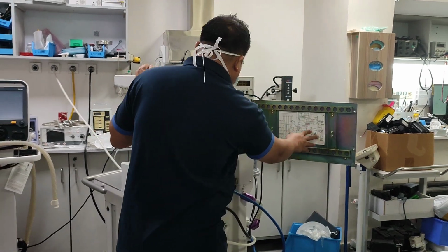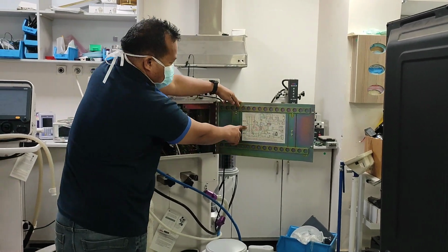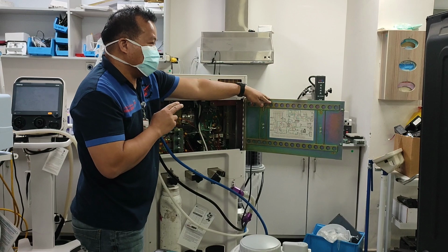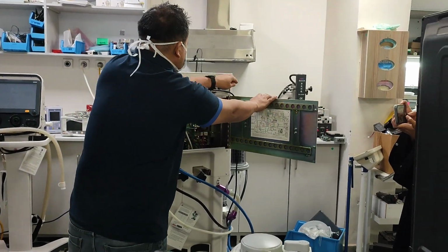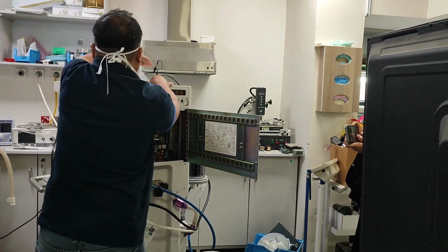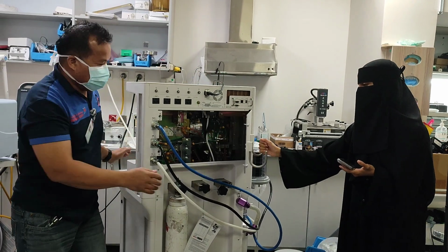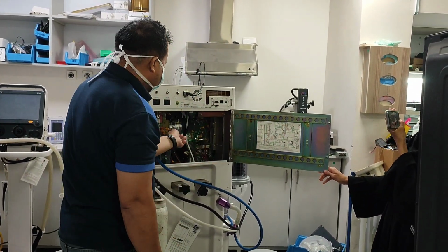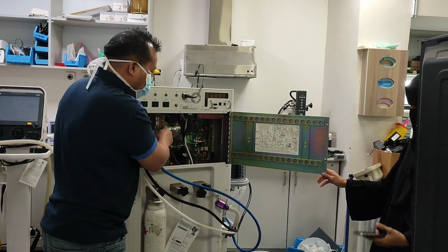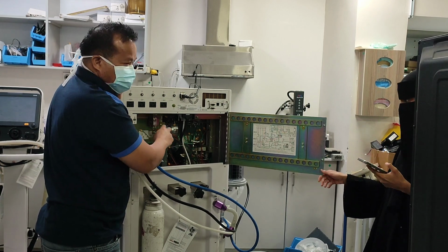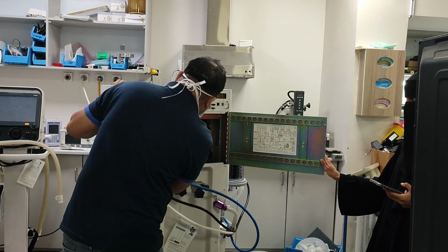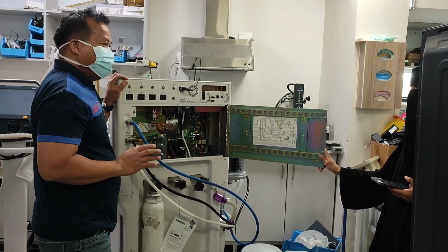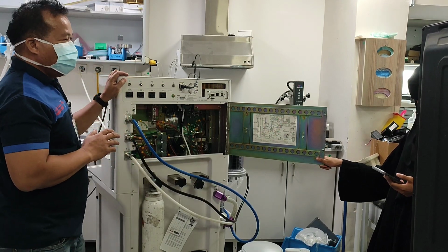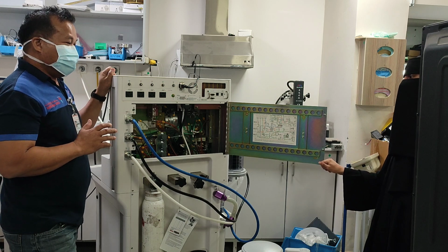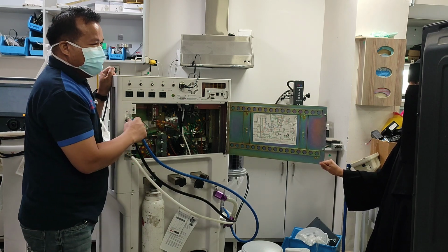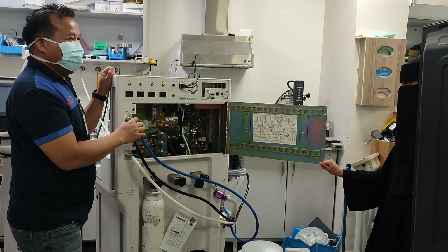So here, you should be familiar with the tubings. There's a color coding here, because it's very important that you do not interchange the tubings. All the tubings are the same size. You can put this one in another connection here, but it is not correct. It's very important that you do not interchange the tubing. For example, number 31 here should be connected correctly. As a new biomed, a future biomed, maybe you will work in the field or in the hospital. For the anesthesia machine, you must not interchange the tubings, because a big disaster will happen.